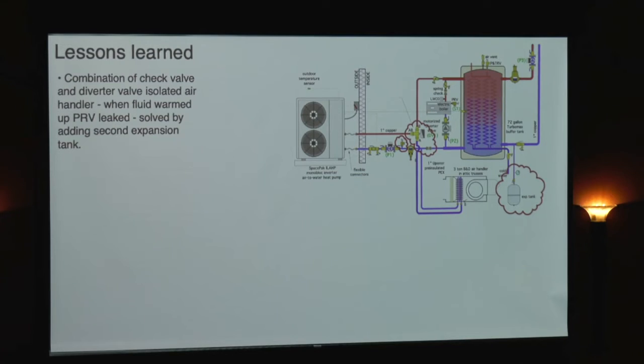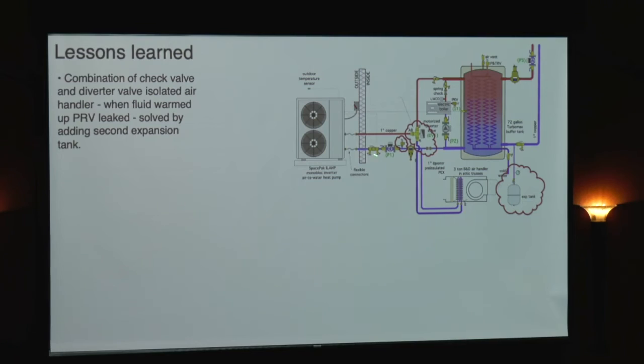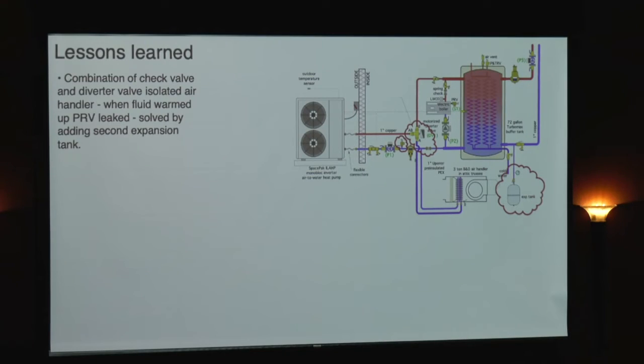Water's an incompressible fluid, and so is 30% antifreeze in water. So we're standing around thinking, oh boy, now we got to open this piping, drain the antifreeze out, and... Fortunately, we found a Band-Aid, and I'm going to call it a Band-Aid because I should have caught this earlier. Right here, there is a dual port purging valve. That's 2 hose bibs, one on either side of a ball valve. So what we did is we bought a high-quality washing machine hose and I think it was an Amtrol 15 tank, and we put another expansion tank in, and it solved the problem.